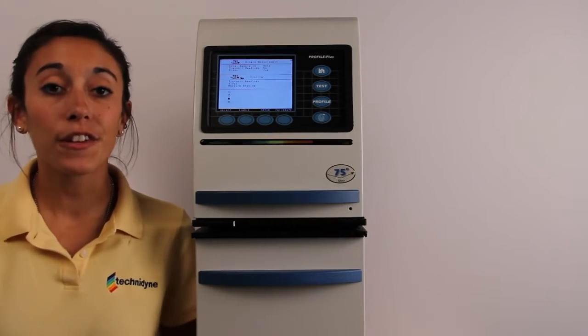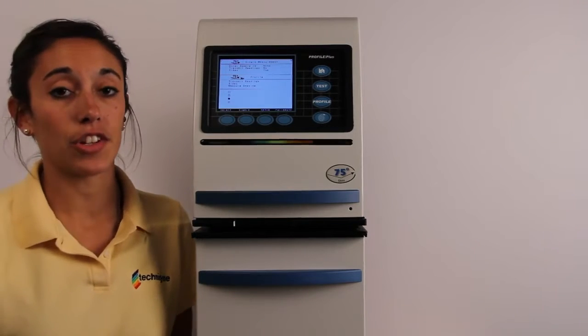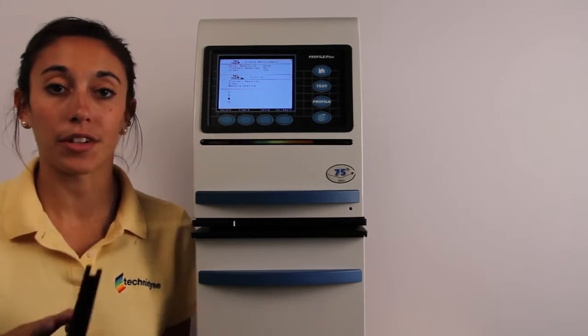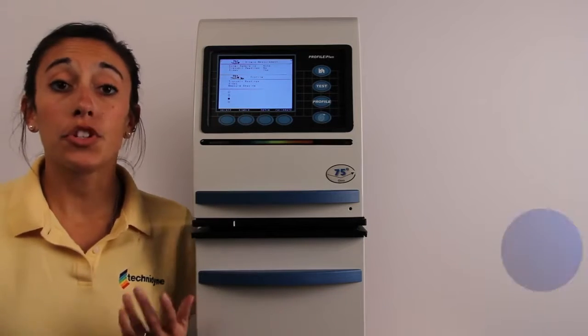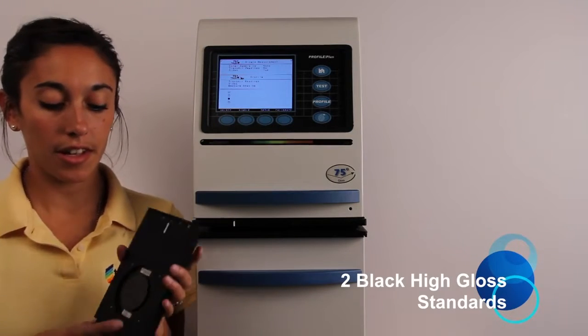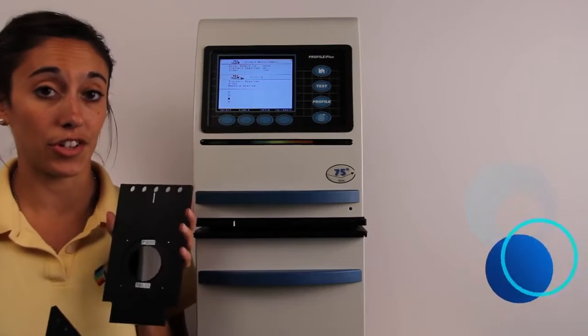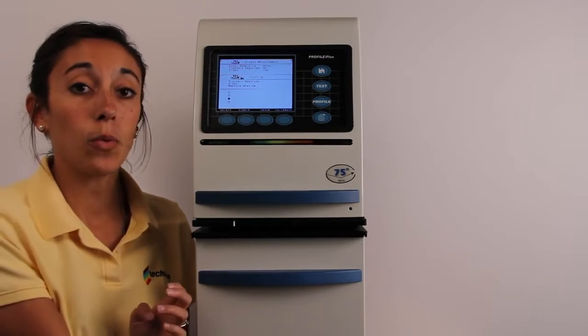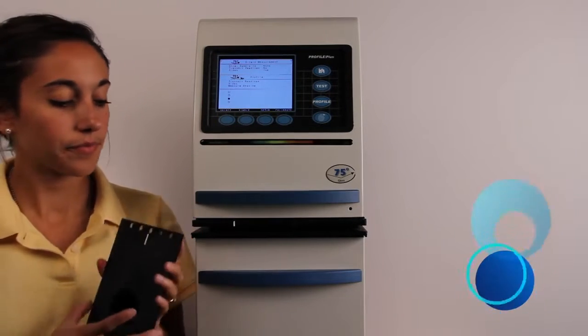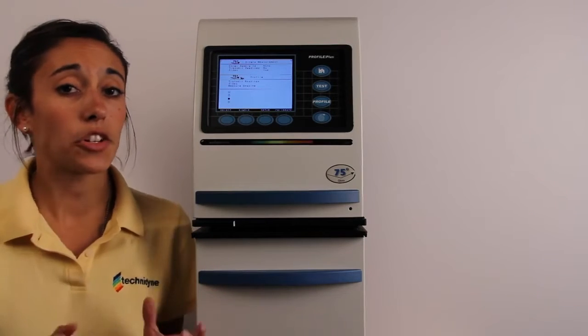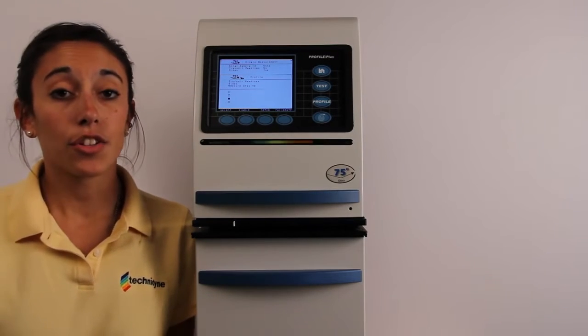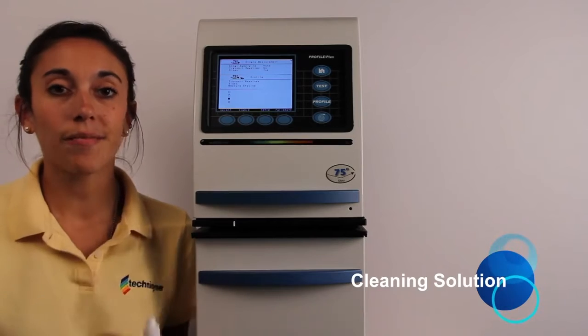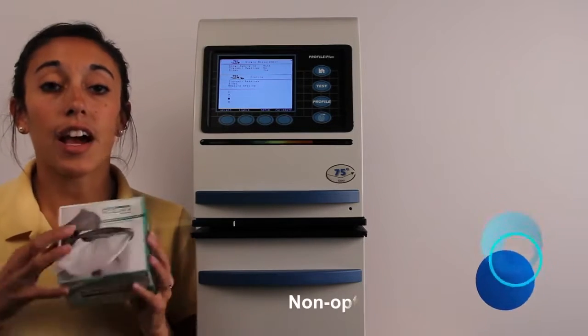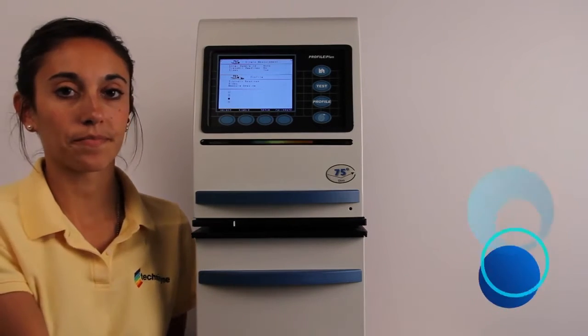Today we're going to talk about Technidyne's Profile Plus Gloss. But before we get started, it's important to make sure that we have a few things on hand. The first thing that you should have are the 3 permanent standards that came with your instrument. There should be 2 black high gloss standards, the primary standard and the cross-check standard, and there should be 1 low gloss standard. Now, it's important to make sure that those black standards stay clean, so you'll want a cleaning solution, and you'll want a non-abrasive, non-optically brightened cleaning wipe.